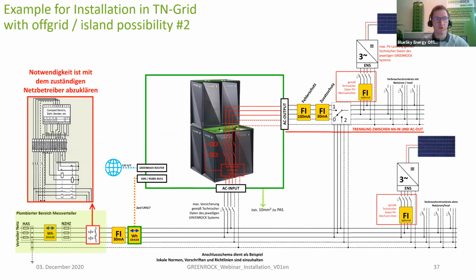But if you have a bigger PV, you can also just combine all the functions. So you have here a bigger PV plant and here a smaller one, which is able to run also during backup. But also in this schematic, the standard function stays the same. First, the system waits until all the loads are covered, and if energy would go into the grid, the battery starts charging. And if energy would come from the grid, it starts discharging. But now what we also need to talk about is that we cannot ensure a 100% off-grid system in that case. Because, for example, if the grid fails at midnight and the battery is already empty at 4 o'clock AM, then when the battery is empty, you will not have a voltage on the AC out.